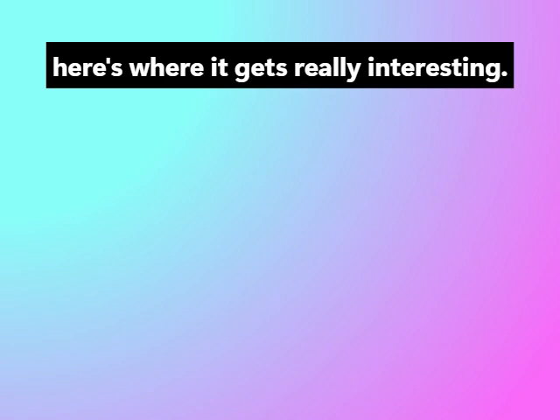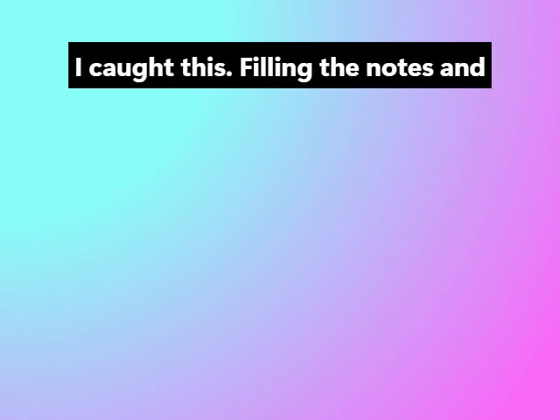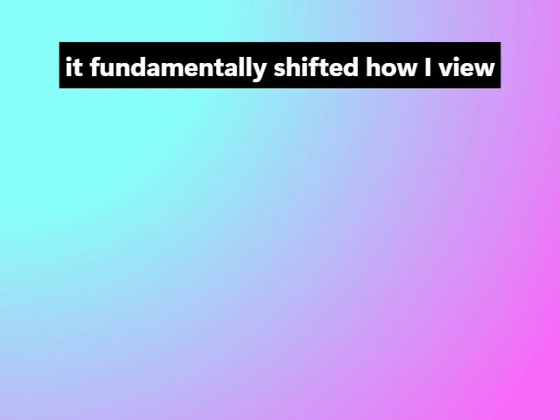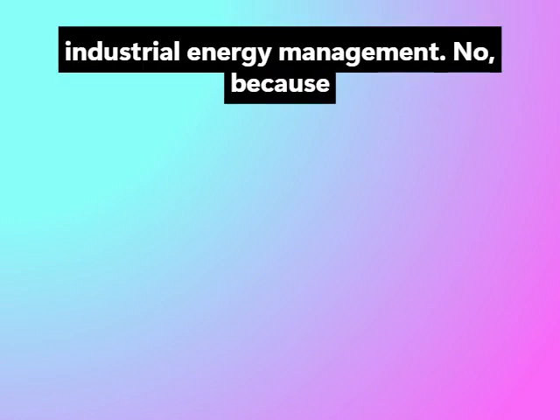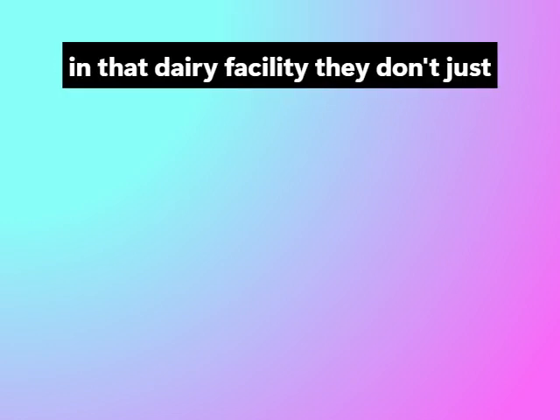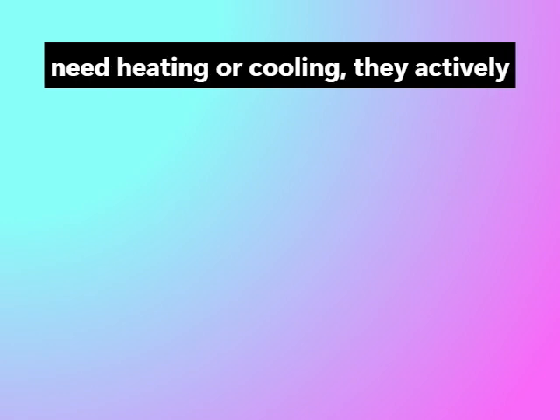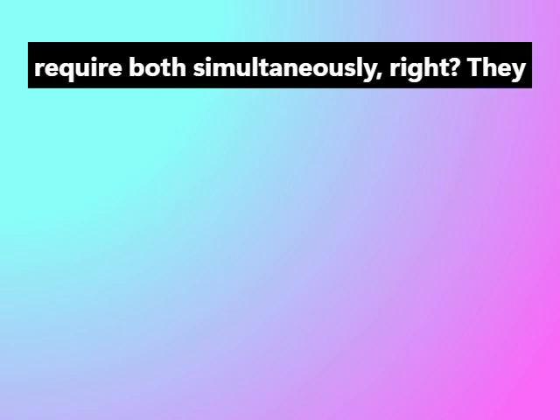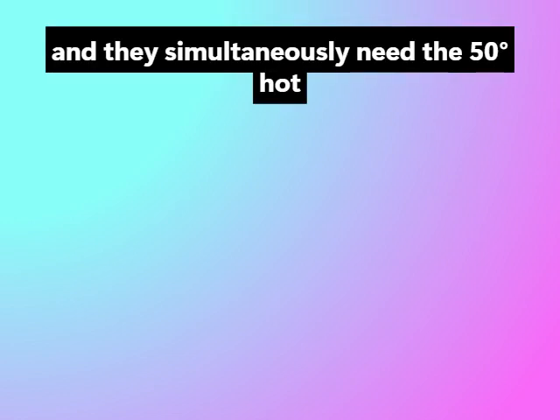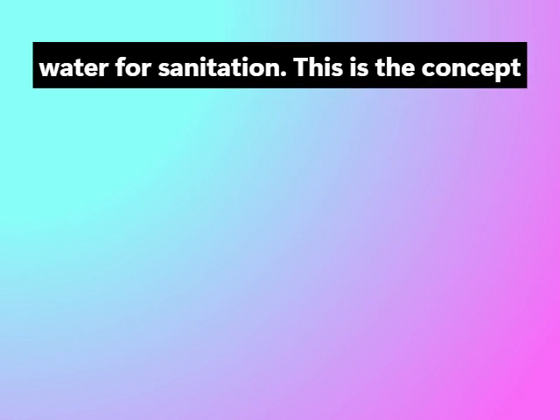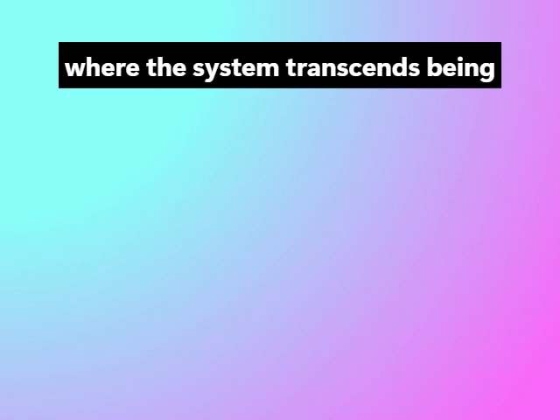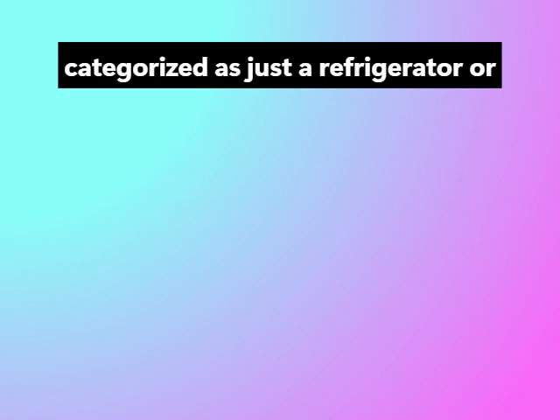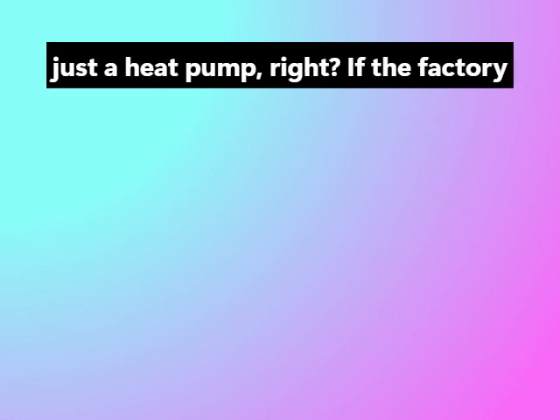Here's where it gets really interesting. I caught this detail in the notes, and it fundamentally shifted how I view industrial energy management. In that dairy facility, they don't just need heating or cooling, they actively require both simultaneously. Right. They need the 10-degree chilled water for storage, and they simultaneously need the 50-degree hot water for sanitation. This is the concept of simultaneous heating and cooling, where the system transcends being categorized as just a refrigerator or just a heat pump.